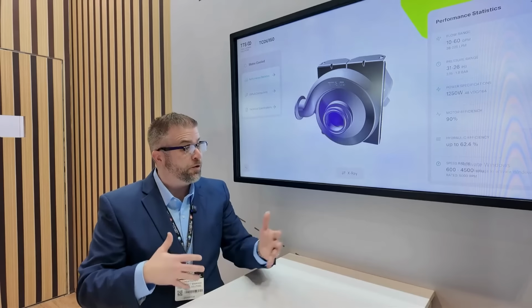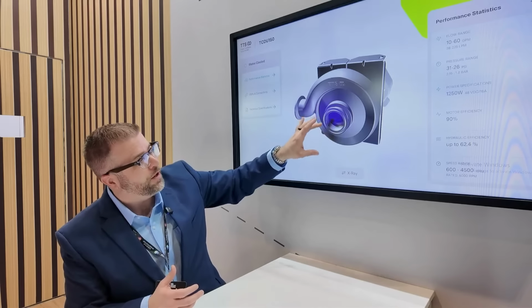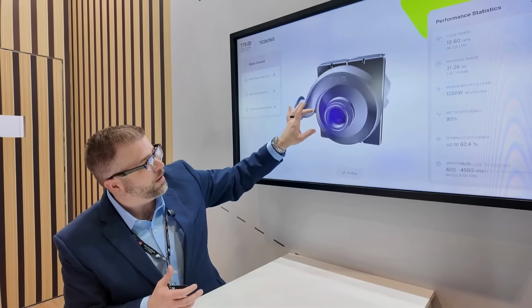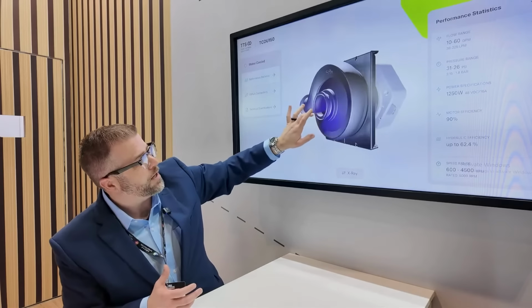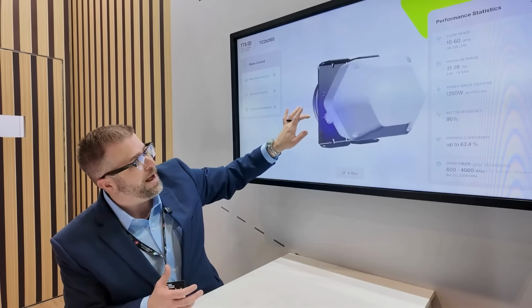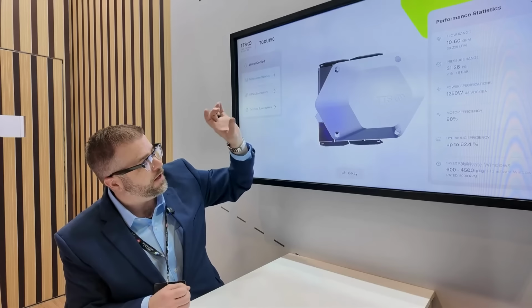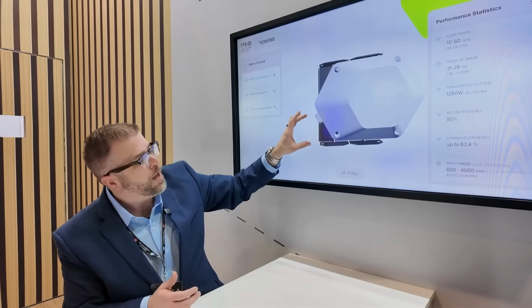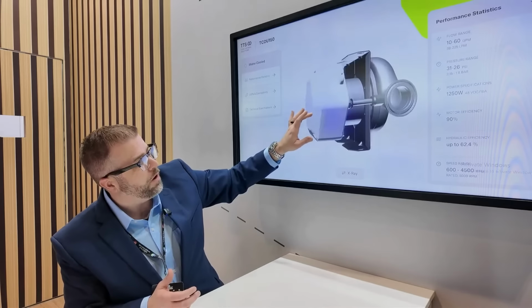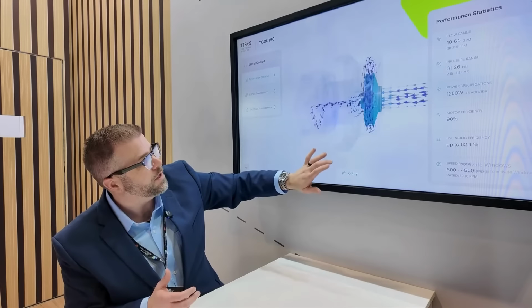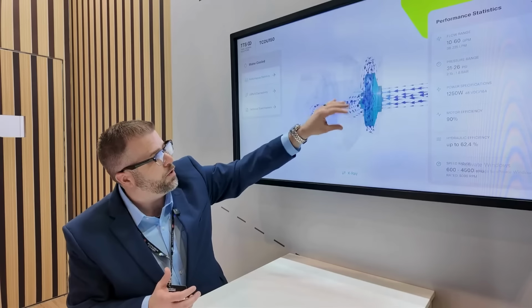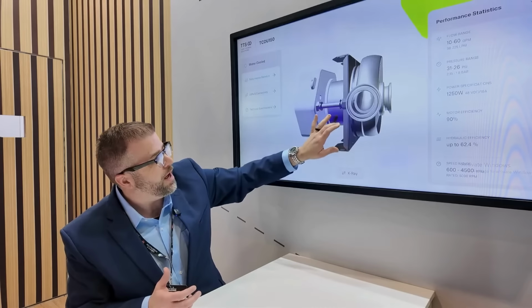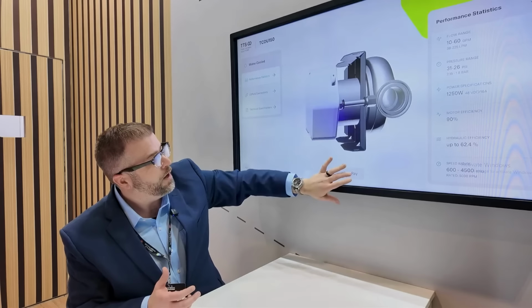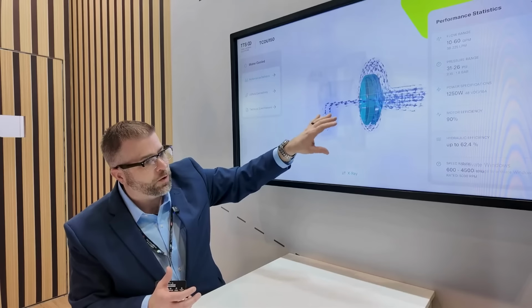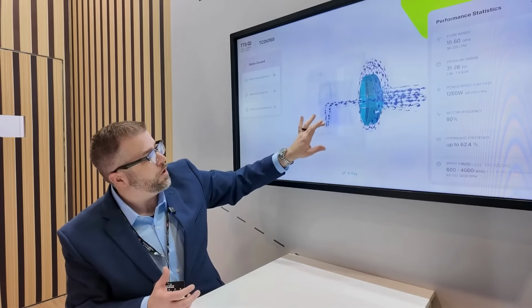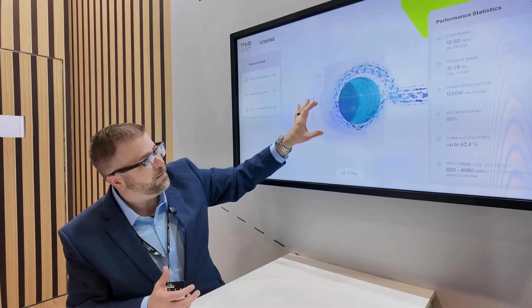Specifically with the TCDU series, we do have one feature that is a bit of a differentiator that we like quite a bit. So as we look at the TCDU here on the back side, we will see the motor and the PCB. What we have done here at Tark is use the inlet and cooled fluid moving through the impeller. We've got a crossover tube here where that cooled liquid is not only cooling the rack and the chipsets, but it's also cooling the PCB and the motor.